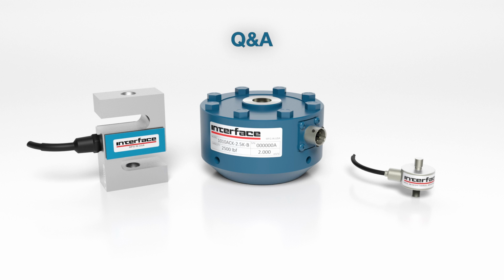Yeah, I want to touch on that. We get that asked again quite often about whether the customer can use that overload range. We really don't recommend it. Over repeated use, it can affect the performance of the load cell. So while it is safe, we recommend you properly size the capacity to be the limit, because again, we can't guarantee performance. Also, linearity and hysteresis are guaranteed up to the capacity. Anything above that, you may lose confidence in that data.